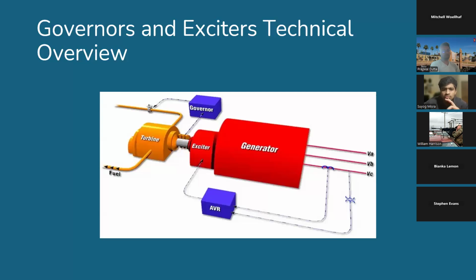Despite the capabilities of PSCAD, however, we have encountered several challenges in simulating diesel generators specifically. While PSCAD has multiple built-in generator models and governor models, none of them are parameterized specifically to control a diesel engine. Diesel generator models require detailed prime mover characteristics, such as fuel consumption curves, which are not always well documented. Additionally, PSCAD synchronous machine models come with limited and sometimes unclear documentation, making it difficult to understand their internal workings. One of the biggest hurdles has been implementing ISO and droop modes correctly within the simulation.